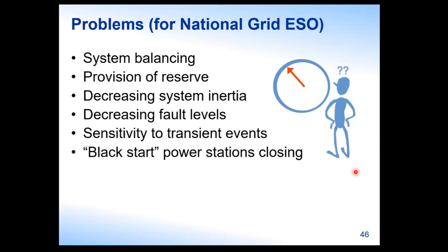I think this is the last point: black start. If there was a national blackout, in order to recover from it we need a reasonable number of power stations able to start up from shutdown with no external power, because they've got batteries and diesel generators that can provide the initial power, and they've got to operate in the rather chaotic system that happens when they try to restore power.